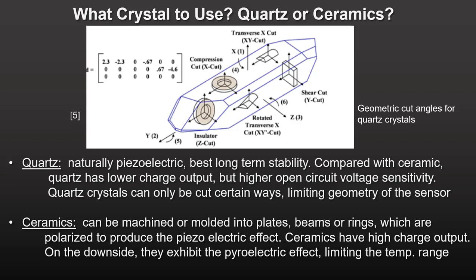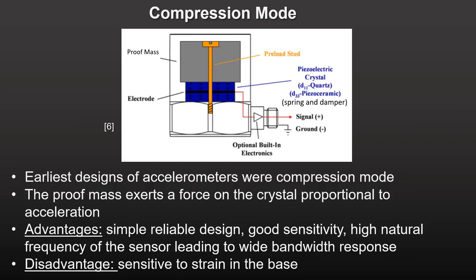Ceramics can be machined or molded into a variety of plates, beams, and annular rings, which are then polarized to produce the piezoelectric effect, providing good dimensional flexibility. They also have very high charge output, compatible with microelectronic charge amplifiers. Ceramics are pyroelectric with a relatively high temperature coefficient compared to quartz, which limits their usage to smaller temperature ranges than quartz, except for some expensive and highly specialized ceramics.